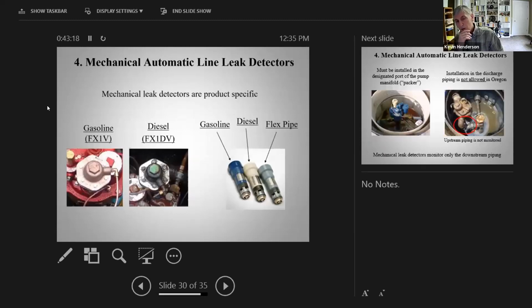We'll just mention that with mechanicals, it depends on what the fuel is. So there are different models of mechanical leak detectors for different kinds of fuel. And with Franklin, they even have a leak detector made specifically for flex pipe or thermoplastic pipe. You just need to make sure that you've got the diesel leak detector in the diesel system and the gasoline leak detector in the gasoline system.